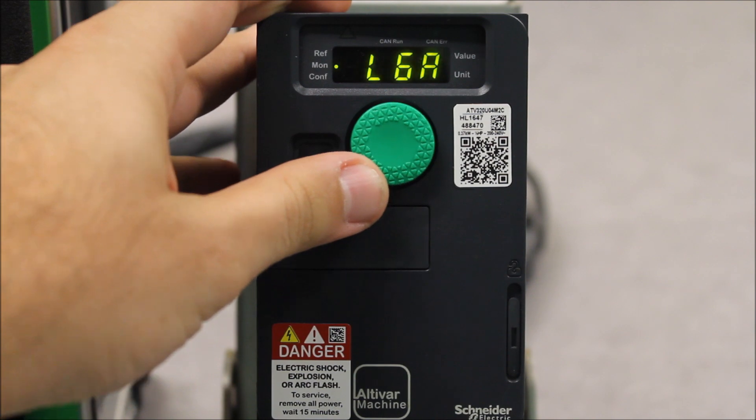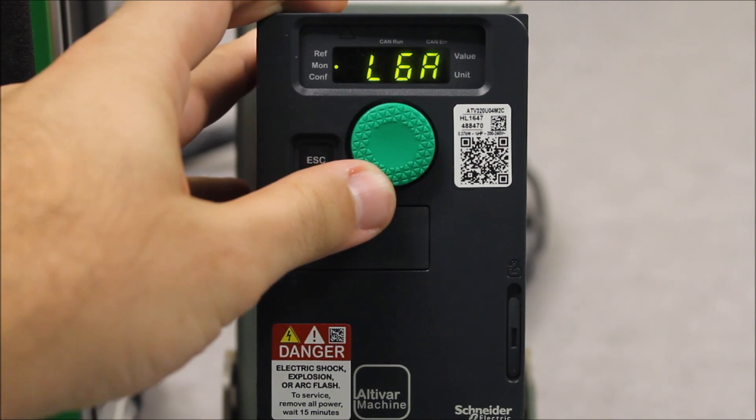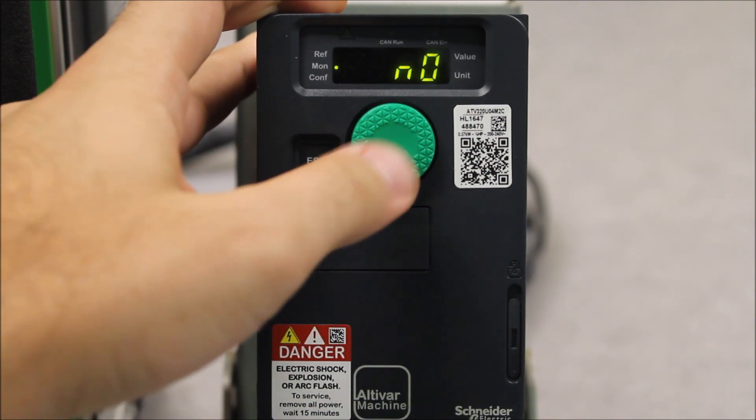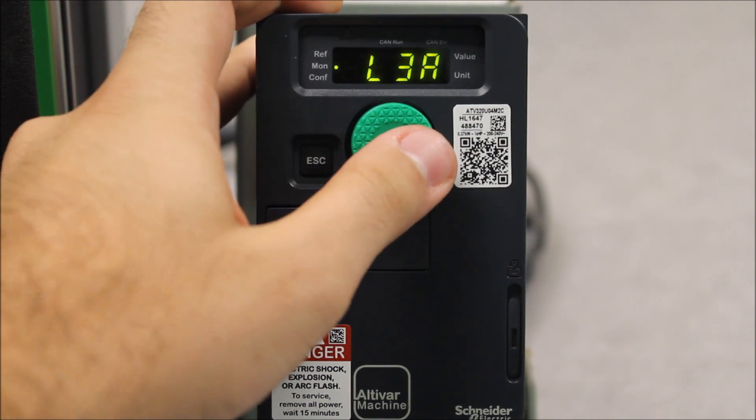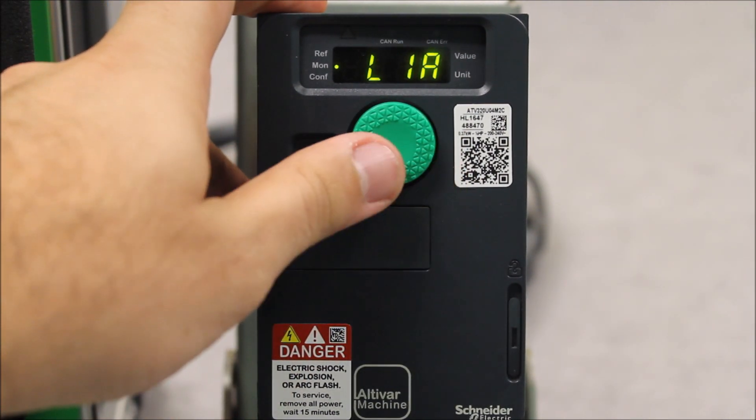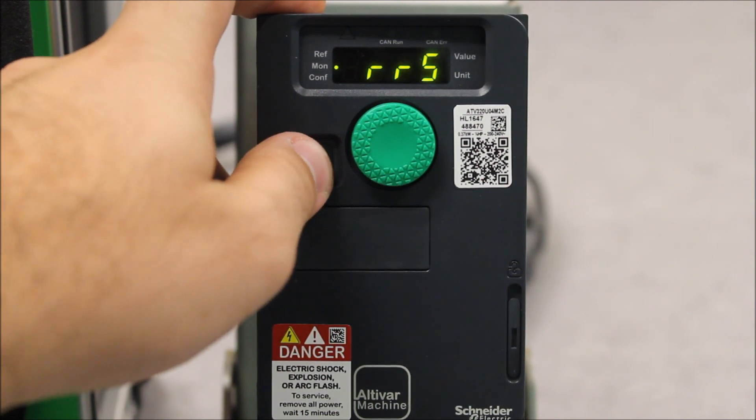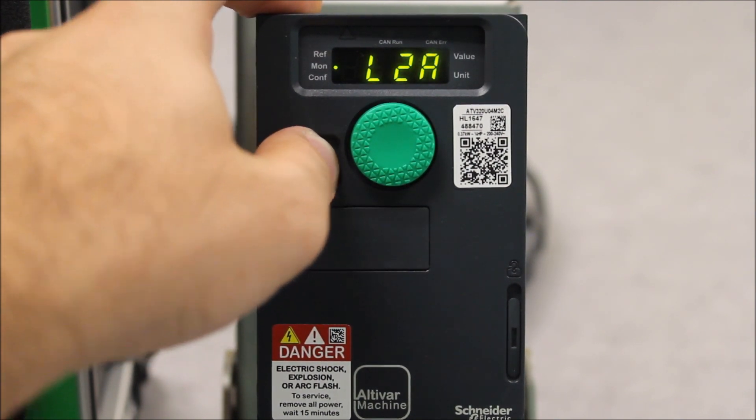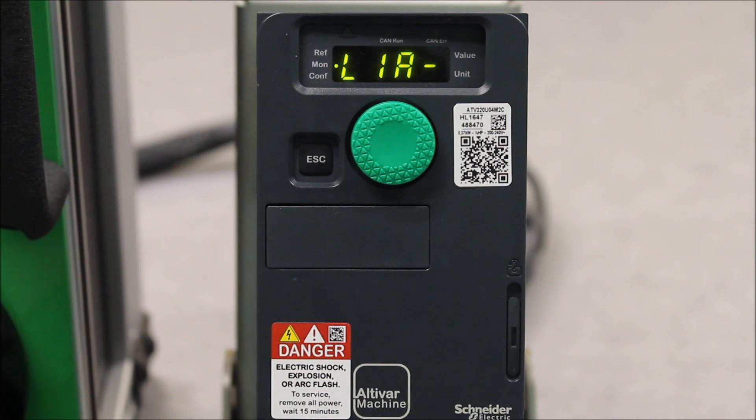it will show L1 through L6A, and if you enter on each, it will tell you what they're assigned to. For example, L1A is a forward direction command, L2A can be reverse.